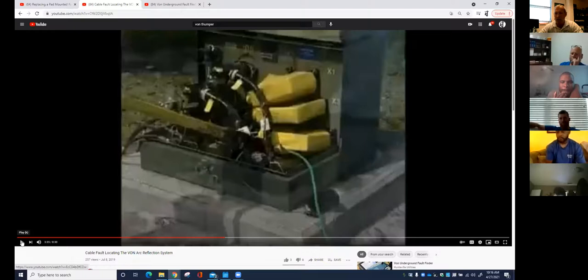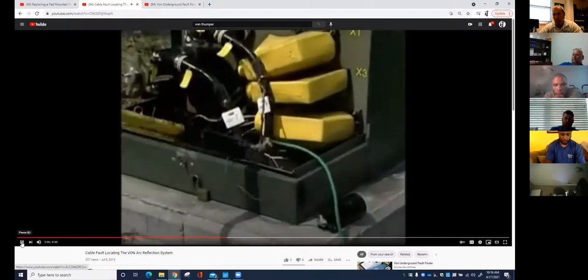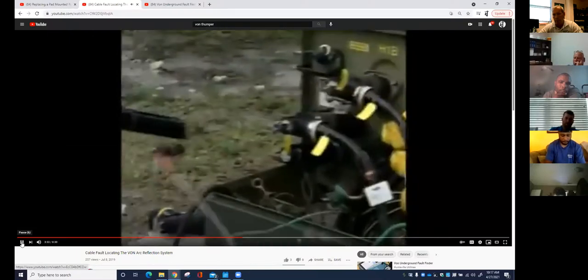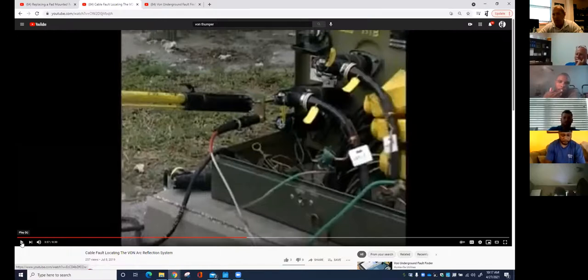Just don't go grounding cable that you're not sure has any voltage. I can tell by the elbow size here, this is 34 kV — so this is pretty high voltage. You want to test before you ground. Just remember to uncoil that green cable completely before you start your machine. Begin by attaching the green safety case ground, then connect the high voltage return to the concentric neutral on the cable being tested as close as possible to the cable termination point. Next, remove the grounded elbow, and finally insert the brass elbow probe attached to the high voltage lead.